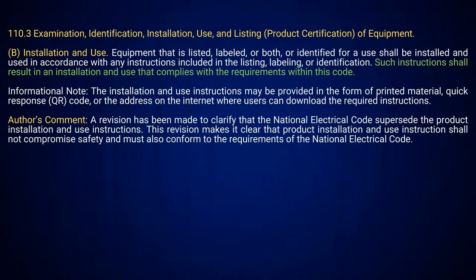To me it seems really contradictory, because the code says use this for examination, identification, installation, and you must comply with that per the code. But then they're saying unless it doesn't agree with the code. Well, the second part says this revision makes it clear that product installation use instructions shall not compromise safety and also conform with the requirements of the National Electrical Code.